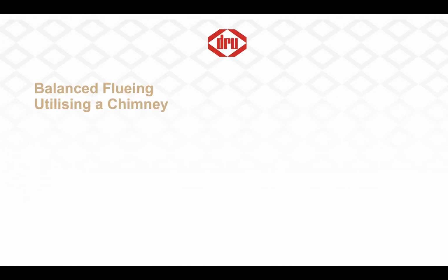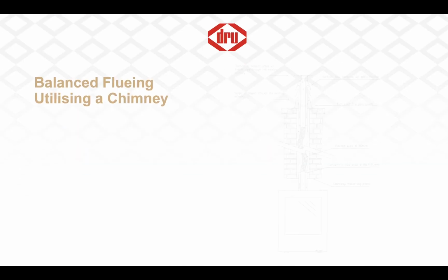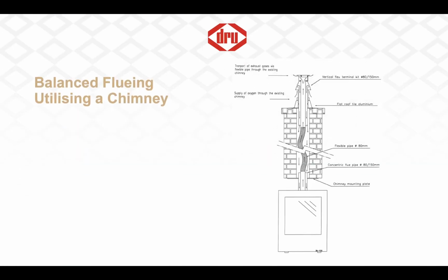Here we can see how a chimney can be utilised in a balanced flue installation. A flexible flue pipe is extended from where the initial concentric pipe penetrates a chimney closure plate. This flexible flue has a diameter corresponding to the initial exhaust pipe diameter, generally 100 mm, and runs the length of the chimney to just below chimney pot level.